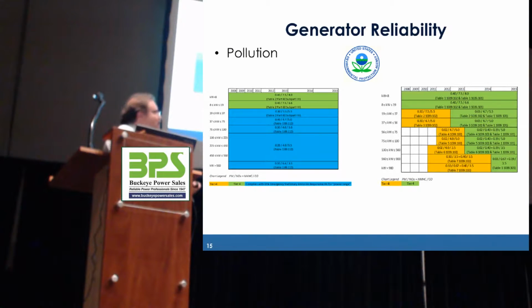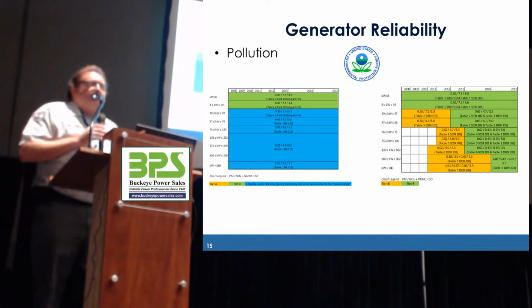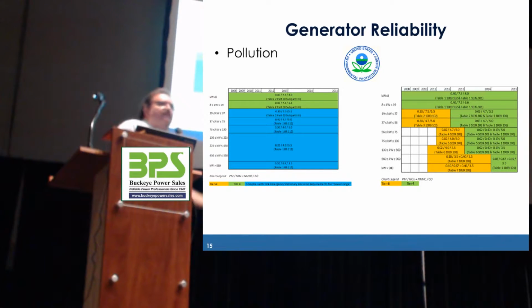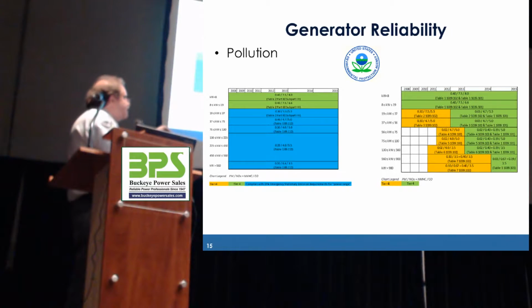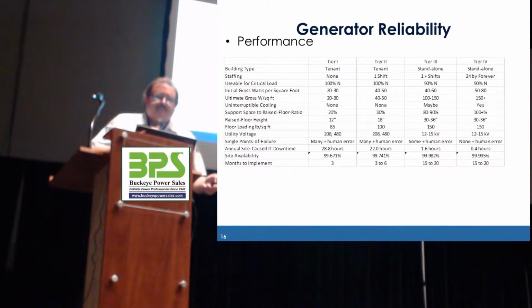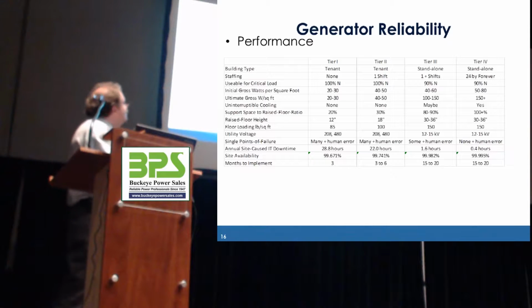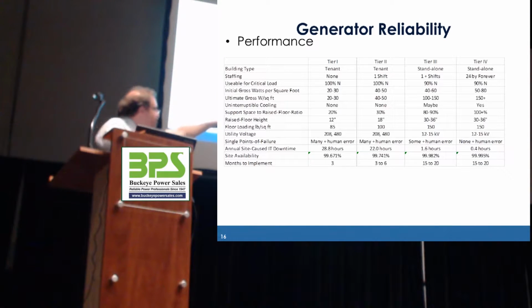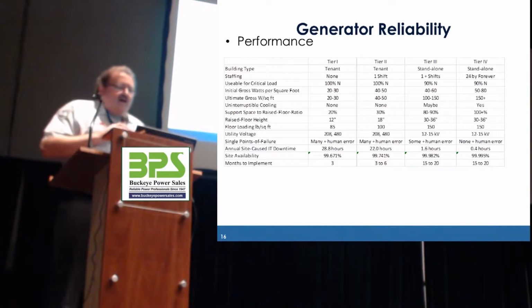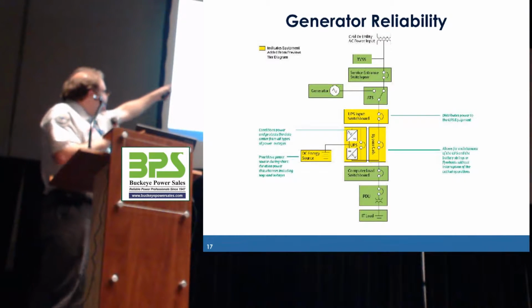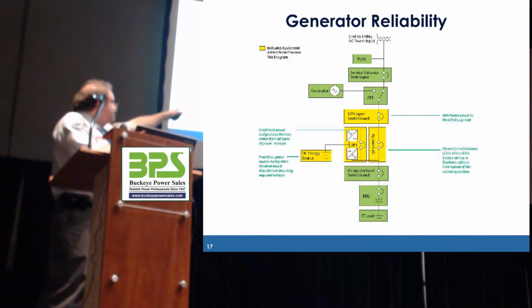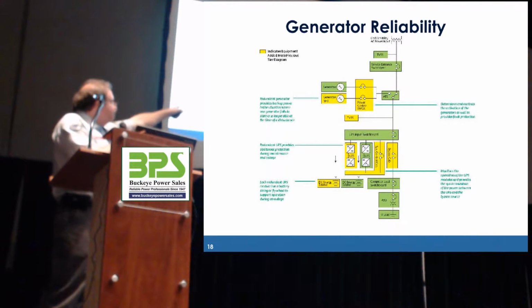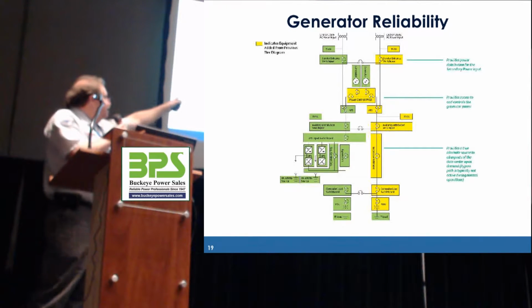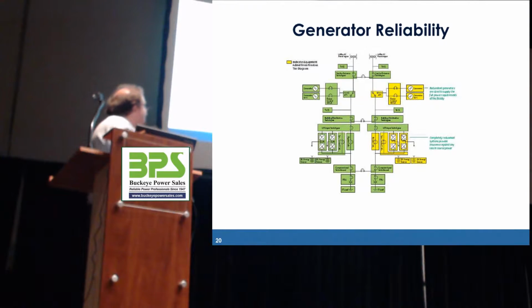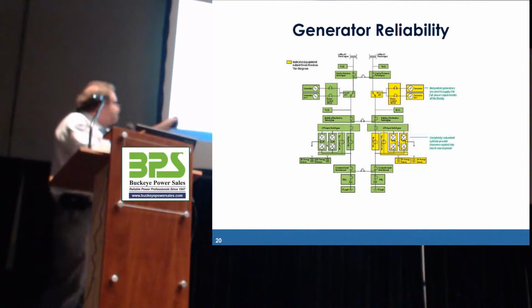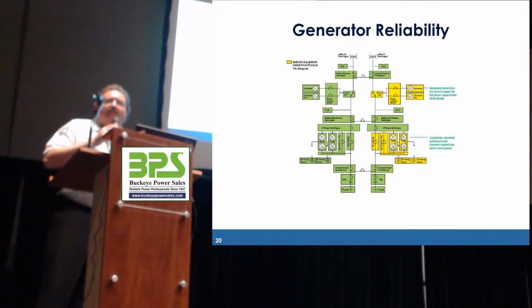It has everything to do with the power system itself. On the generator side, we have tier that has to do with the amount of emissions from the engines. And that's all it is. It has nothing to do with your reliability. From a performance standpoint, for uptime, we talk about the tiers, and that's what gets you at a tier 4, gets you that 99.995% uptime. And just as a quick line diagram, a tier 1 is going to have a single utility, a single generator, and probably a single UPS. A tier 2 could have 2 generators and 2 UPSs. A tier 3 is going to have a second utility, and you may share the generators. And a tier 4 is completely redundant with 2 different sets of generators, 2 utilities, redundant UPSs, the ability to split the bus or tie the bus as necessary.